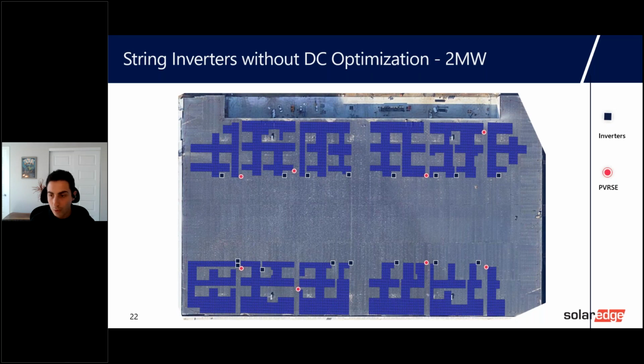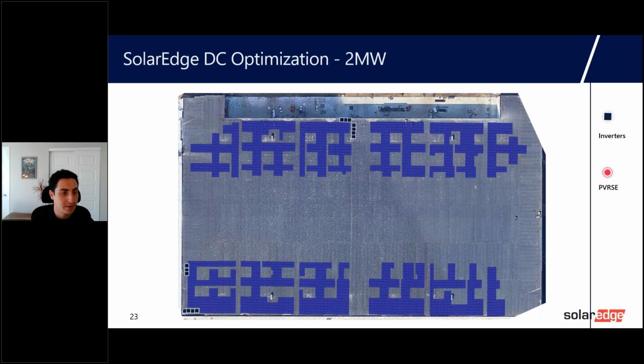Due to fire code requirements, there need to be setbacks, there need to be walkways, so you're almost always going to have subarrays in a rooftop system like this. And the way to remain code compliant when using a non-DC optimized system is the use of PV rapid shutdown equipment, listed PV rapid shutdown equipment. That can take a couple of different forms we'll talk about a little bit more later, but you can see those are also going to be distributed throughout your array to maintain compliance throughout the entire system.